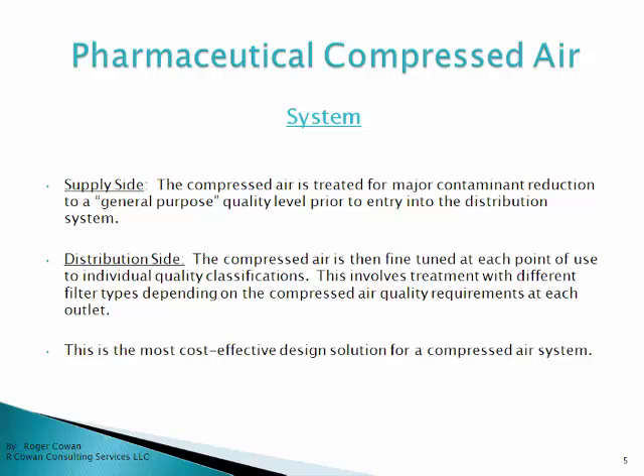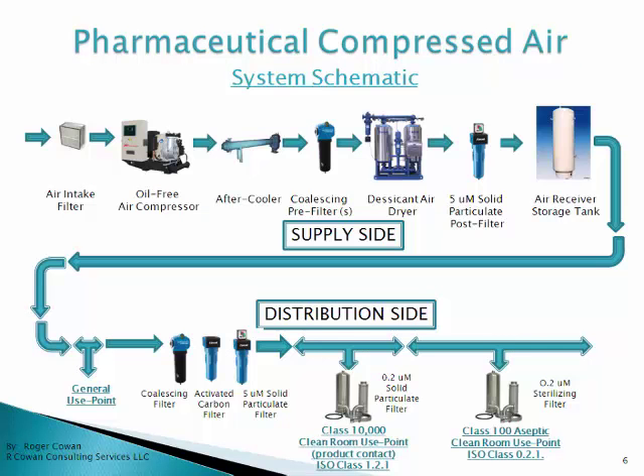On the supply side, the compressed air is treated for major contaminant reduction, bringing the air down to a general purpose quality level before entering the distribution system. On the distribution side, the compressed air is fine-tuned at each point of use, bringing it down to individual quality classifications. This is done by treating the air with different filter types depending on the compressed air requirements at each outlet. This is the most cost-effective design solution — bringing the air on the supply side down to general purpose and then fine-tuning it to different quality levels on the distribution side, as opposed to bringing it all the way down to a very high quality on the supply side.